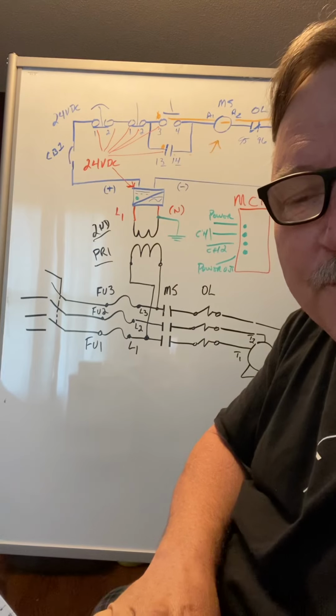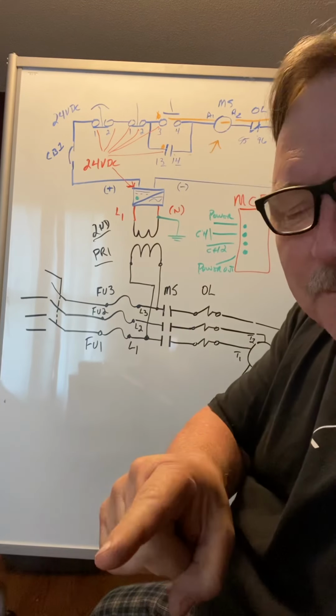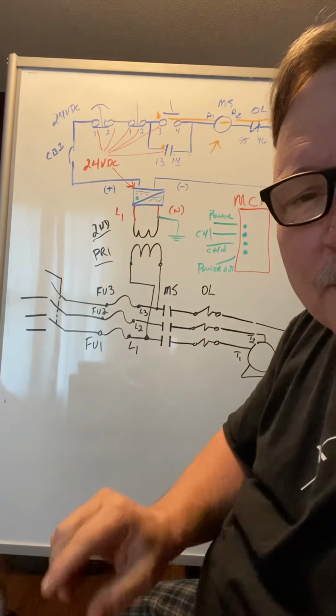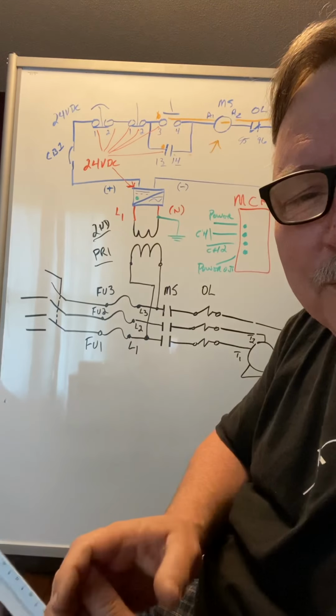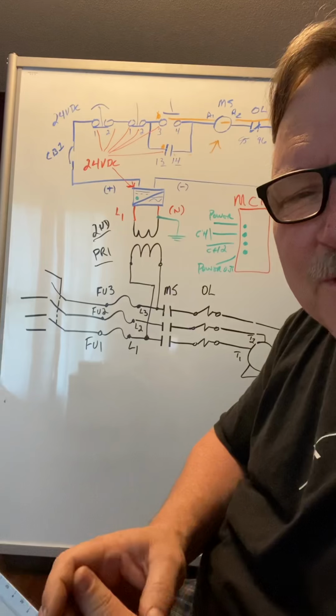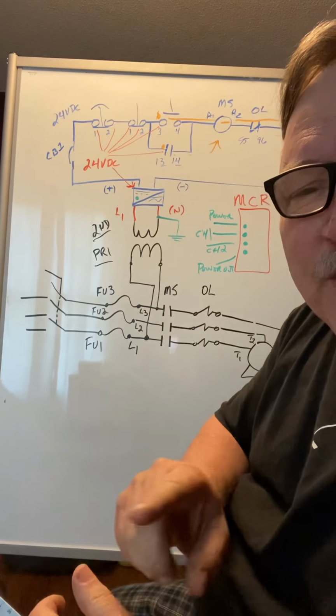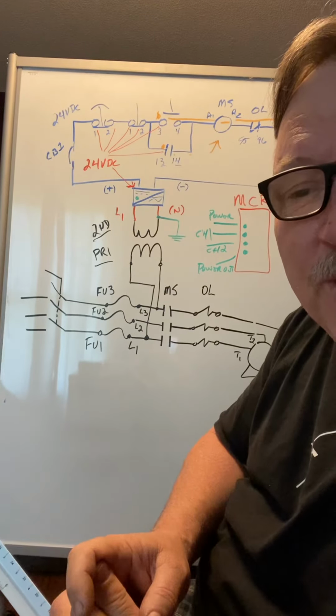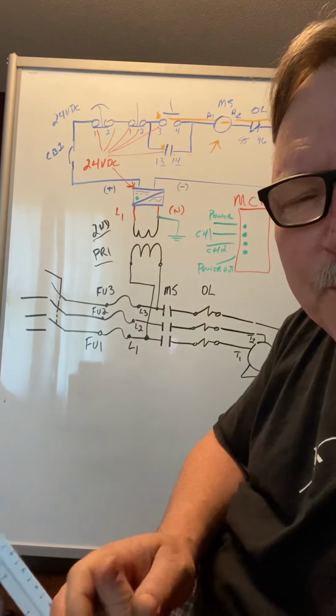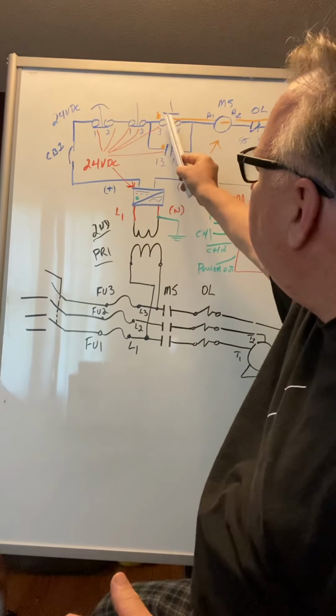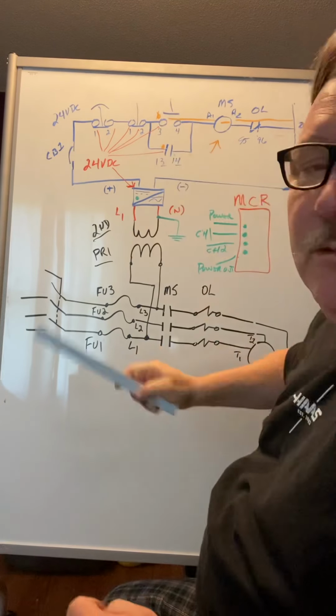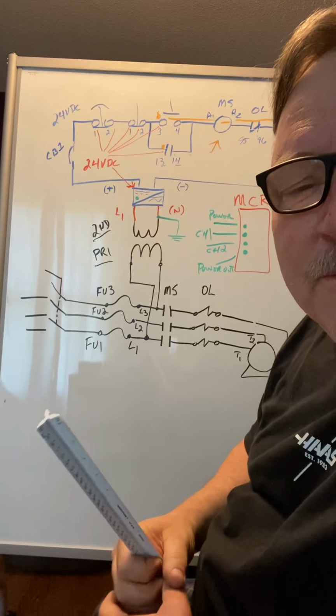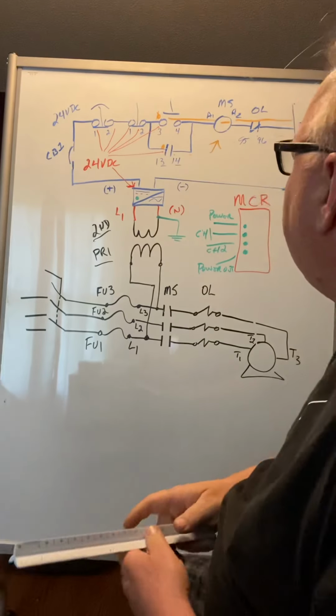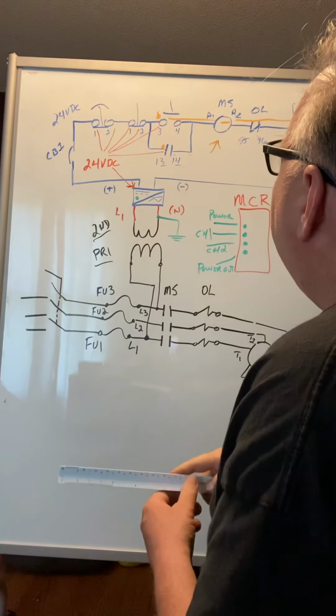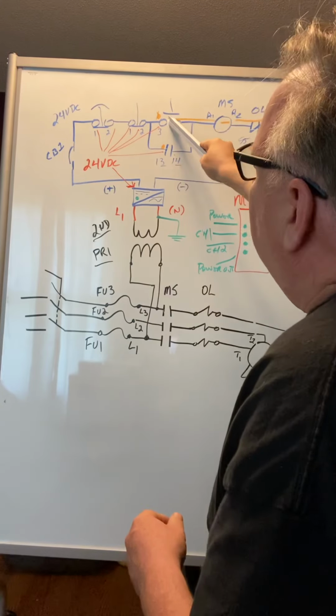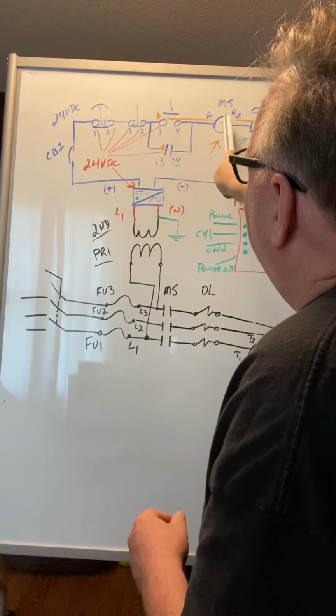Okay, it's counterintuitive, but when you don't see power, that's because the electricity is taking the path of least resistance. A good switch should have about 0.1, 0.2 ohms resistance. Your meter's got about 30 ohms resistance. Okay, but it should go through that. If it doesn't change state or it changes state just a little bit, you got a switch problem. You could also have bad terminations at either one of those 2 switches or those 2 terminals right there. So that's something for you to look at, okay?